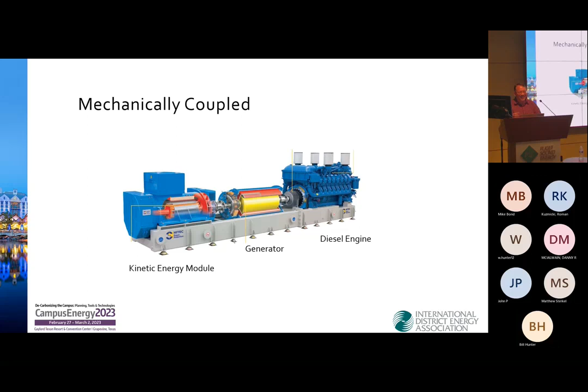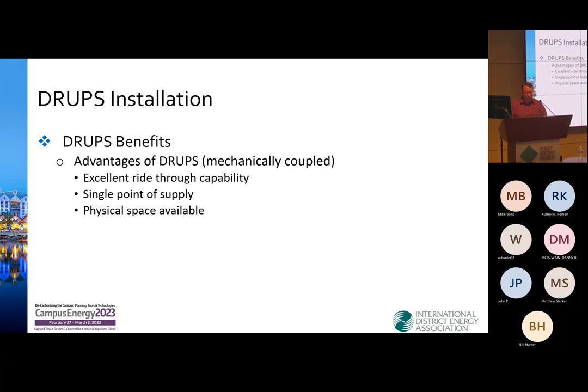So what are the benefits? I kind of touched on it. Excellent ride through. The system is running all the time, so the generator and flywheel are spinning constantly. The generator at 1800 RPMs, the flywheel at 4200 RPMs. It weighs 6 tons, which is a lot of mass, but it's good for 30 seconds max of 2 meg power, more like 25 seconds. But that's more than enough for the diesel engine to start up. Since it's starting unloaded, it will come up to speed and take over driving the generator within 2.5 to 3 seconds. So it was the answer to our problem.